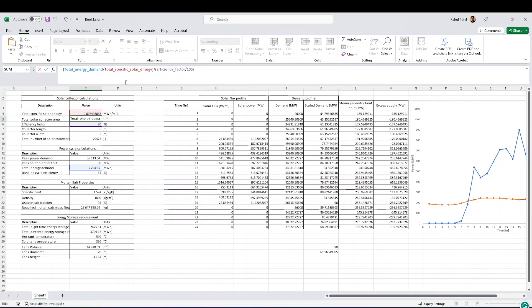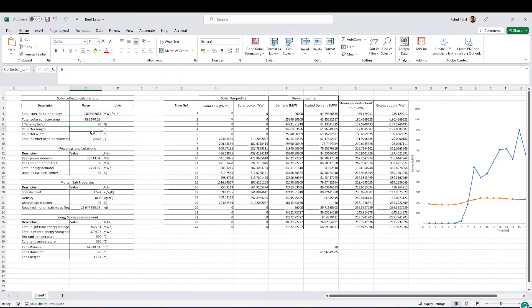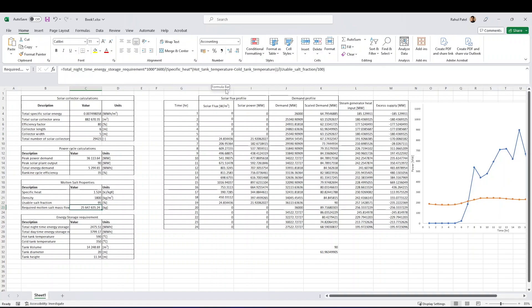We also have solar collector length and width based on manufacturer specifications. Using the solar collector area, we can calculate how many solar collectors are needed to meet the energy demand. This gives the peak power demand. We also have molten salt properties: specific heat, density, and the usable salt fraction — how much salt can actually be used in the system — plus the required salt mass based on simple calculations.